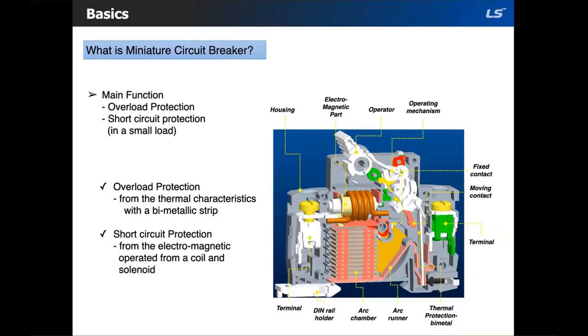There are two arrangements of operation of an MCB. One is the thermal effect of overcurrent, and the other is the electromagnetic effect of overcurrent. The thermal operation of a miniature circuit breaker is achieved with the bimetal strip. Whenever continuous overcurrent flows through the MCB, the bimetallic strip is heated and deflects by bending. This deflection releases a mechanical latch. As this mechanical latch is attached to the operating mechanism, it causes the mechanism to open the miniature circuit breaker. But during a short circuit condition, a sudden rise of electric current causes an electromechanical displacement of the plunger associated with the tripping coil of the MCB. The plunger strikes the trip lever, causing immediate release of the latch mechanism, opening up the contacts.